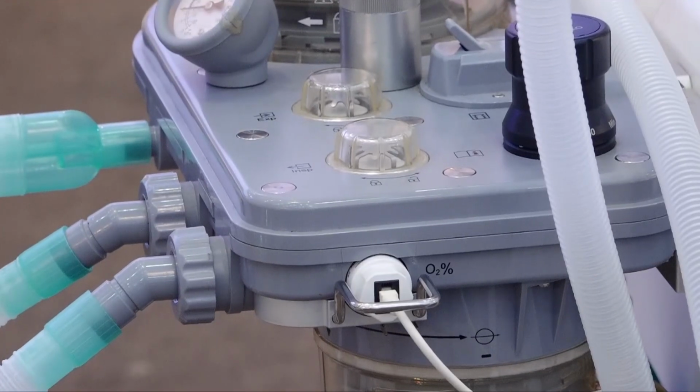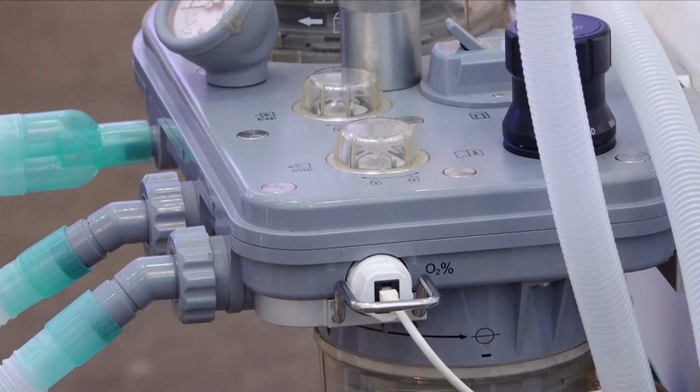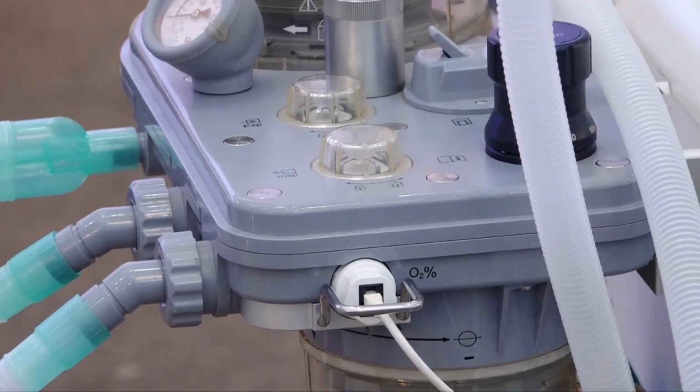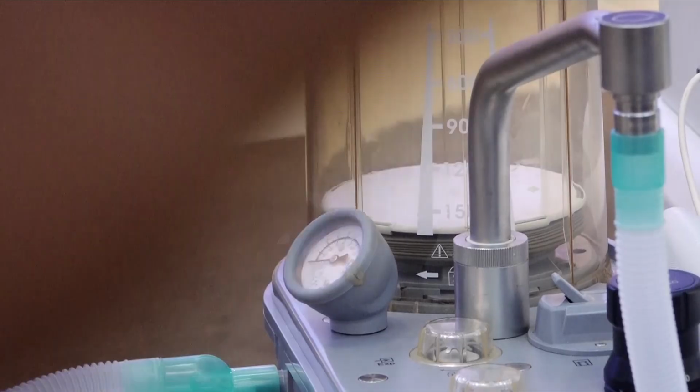Used? No, with confidence you can raise your hand. Why like this? So when we use it, suppose I am holding a mask on a geriatric patient, an edentulous patient, there is so much of leak, or a morbidly obese patient, you are not able to ventilate with a mask. Then you activate it so that you overcome that leak by using extra amount of the oxygen source, that is 35 to 70 liters.